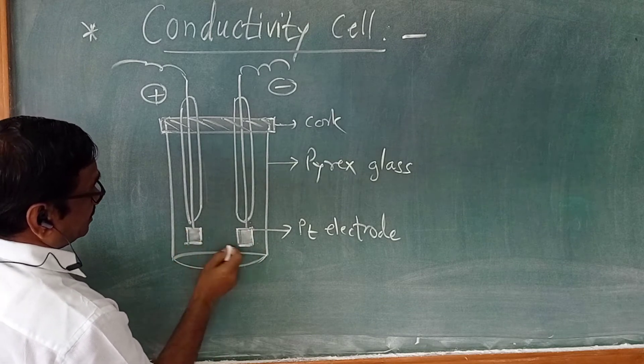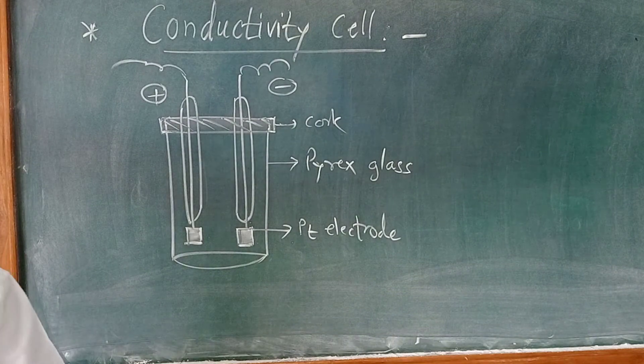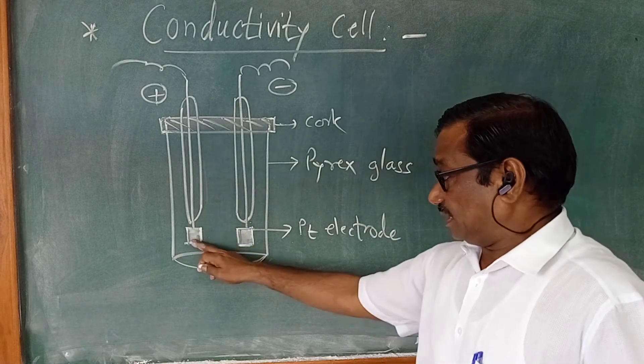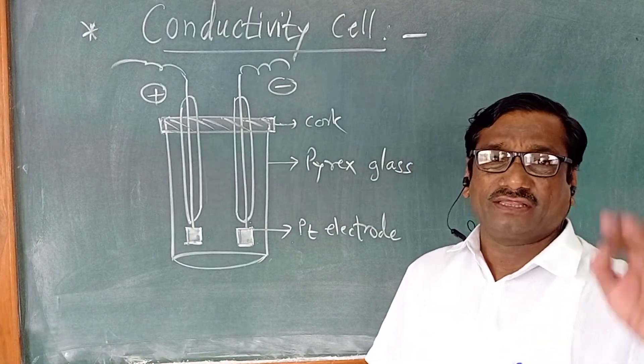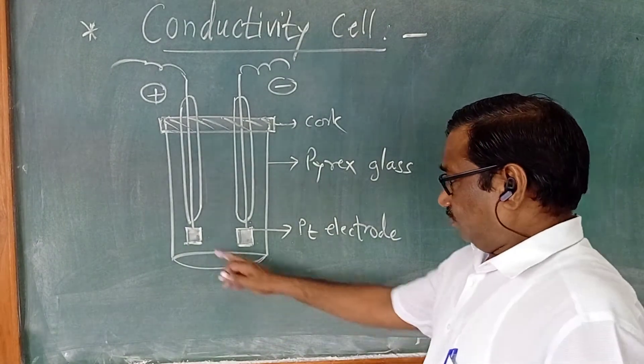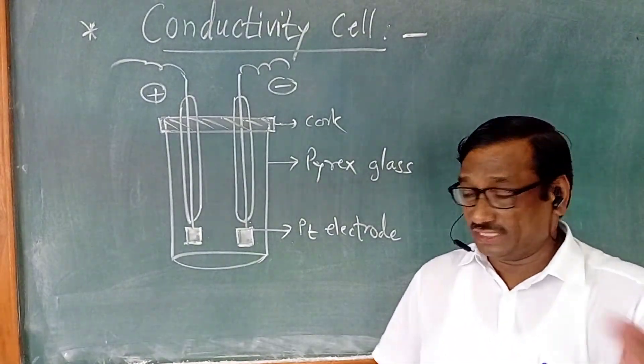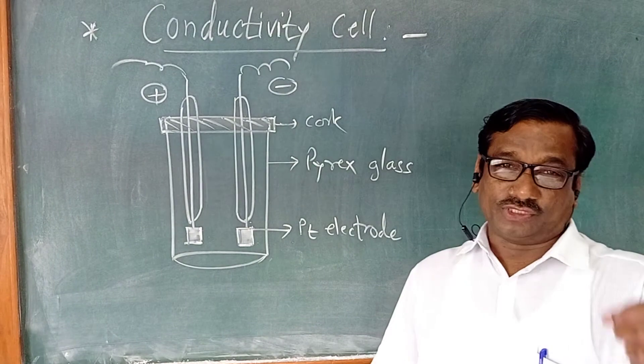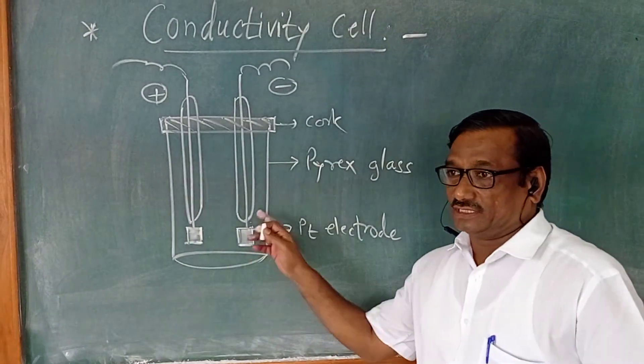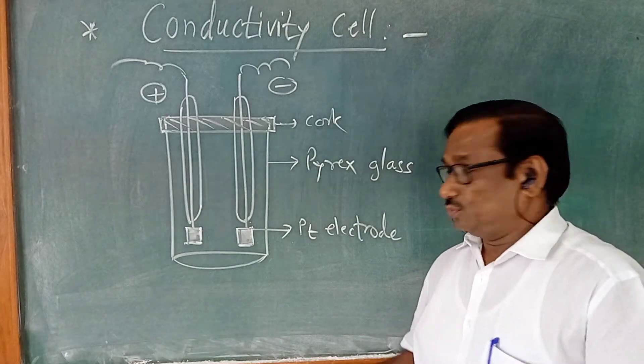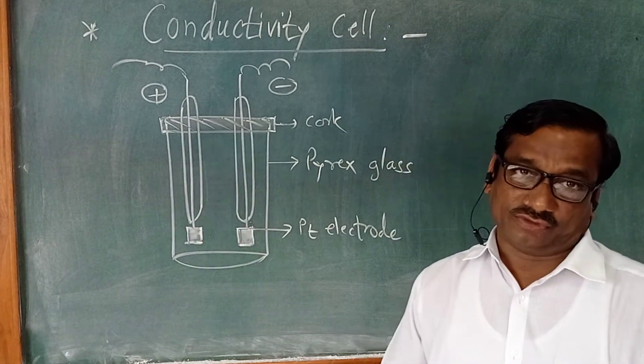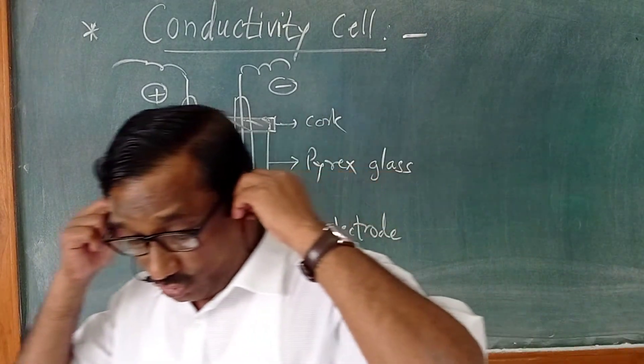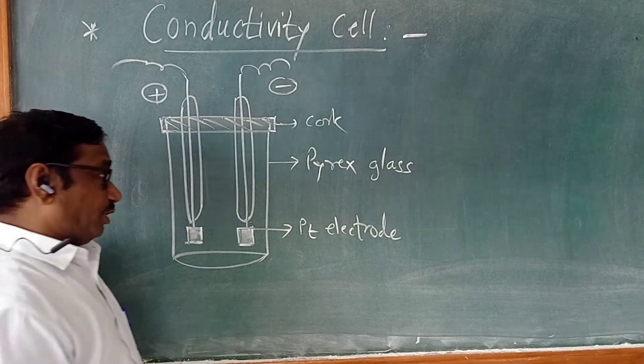The platinum electrodes are at a fixed distance from each other. These are very thin platinum foils which are coated with platinum black. Platinum black is deposited on them electrolytically to minimize the polarization effect.